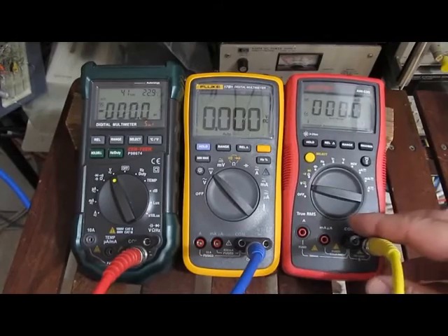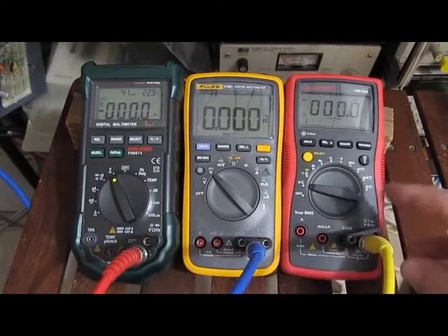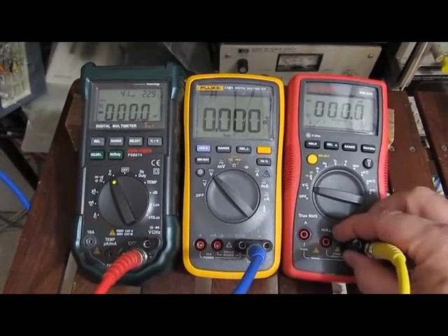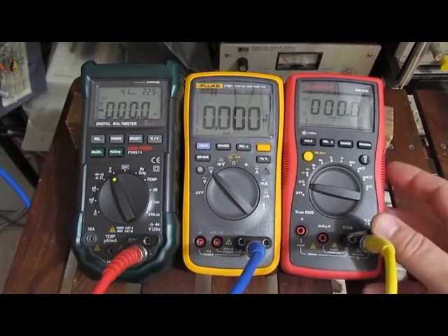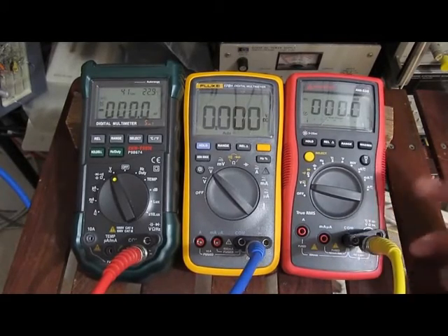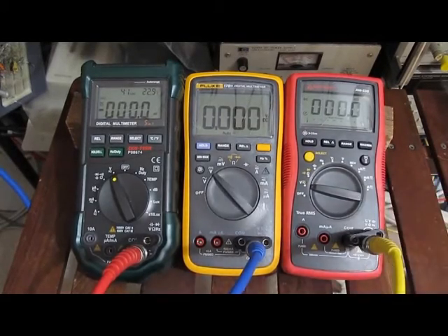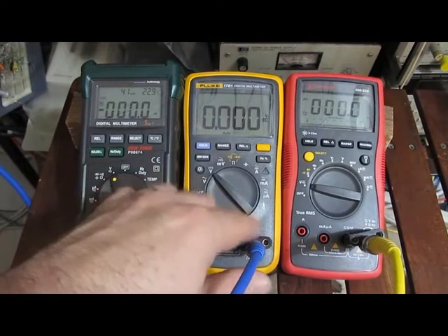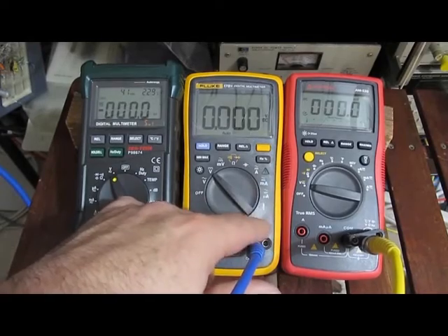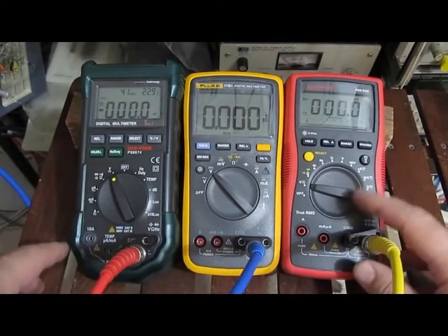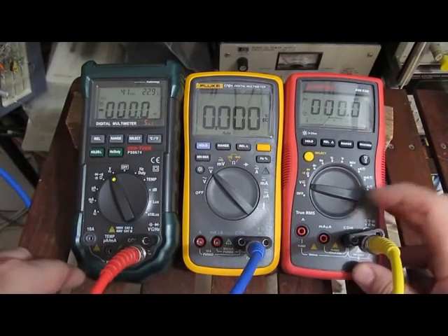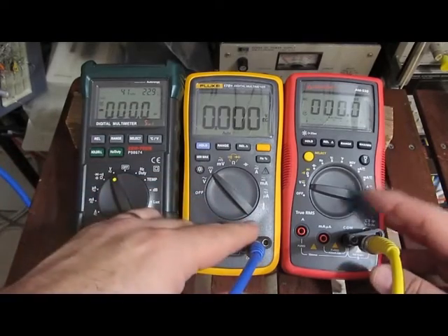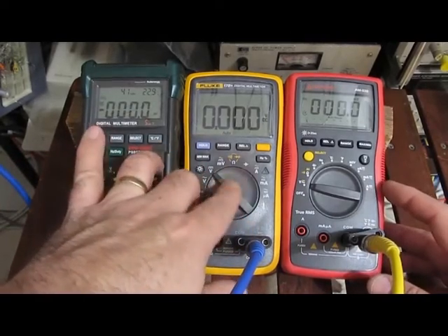I had actually changed the transient generator, so moving forward I can compare the meters, but going back and comparing where the first set of meters was tested and where they would fail against this set is a little difficult. So I'm assuming this Fluke 17B will be much better than this Amprobe AM530, but that's really what we're here to do, is repeat that test.